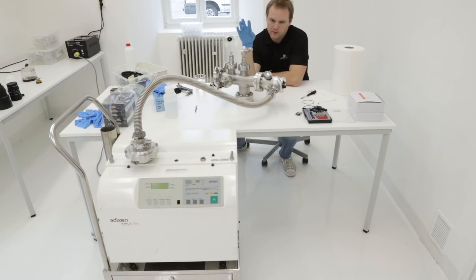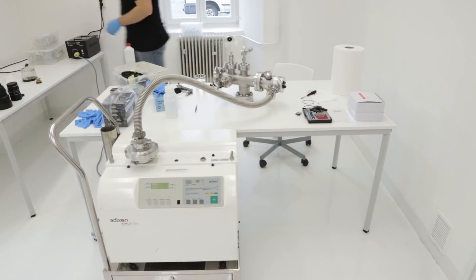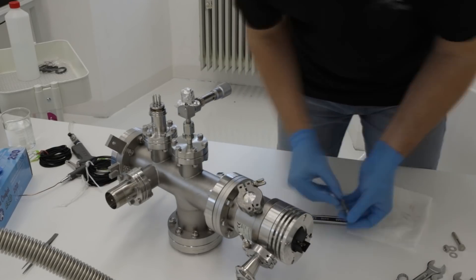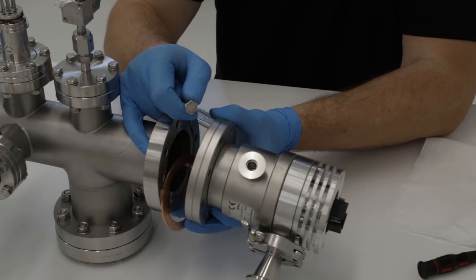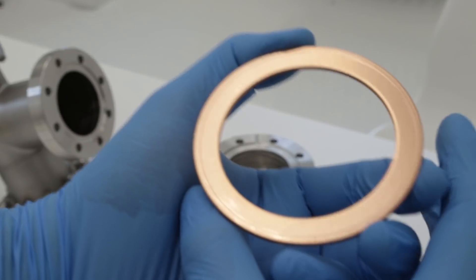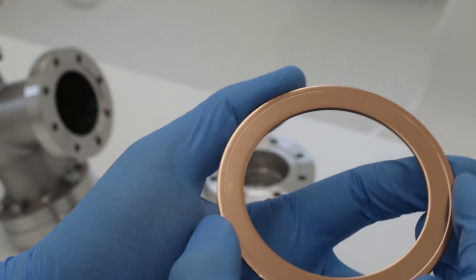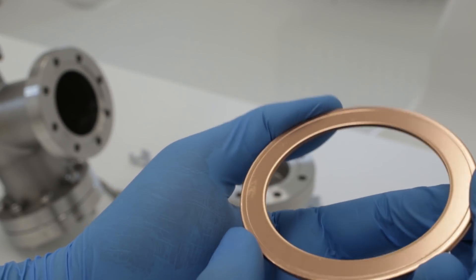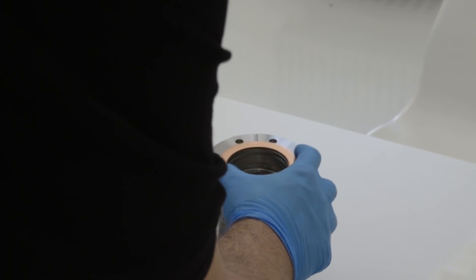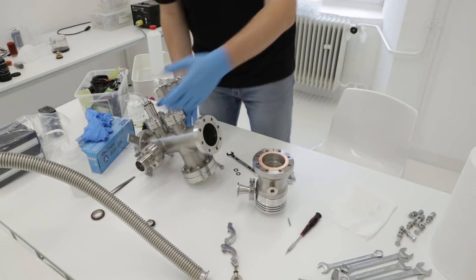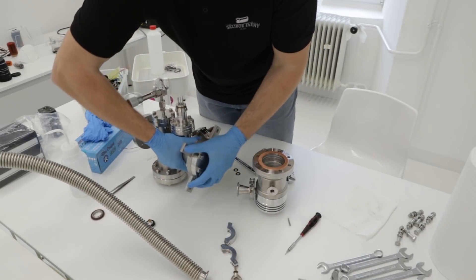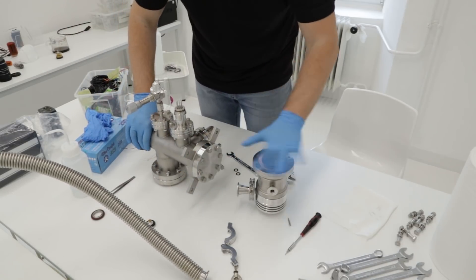Okay, so I'm running out of ideas, so I will remove the turbo from the system and try to connect it straight to the leak detector. Let's do it. This line here is from the knife edge, so there's no rubber, no o-rings, it's just metal to metal connection which is very good. Now we need to take this blanking cover from here and put it here and we'll get a closed system.